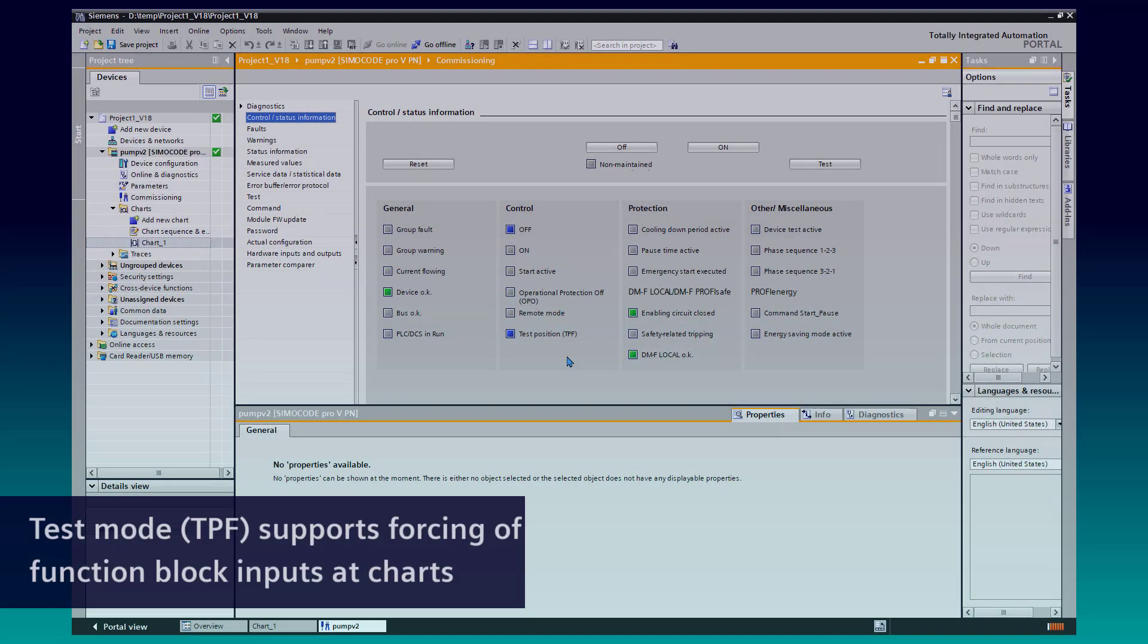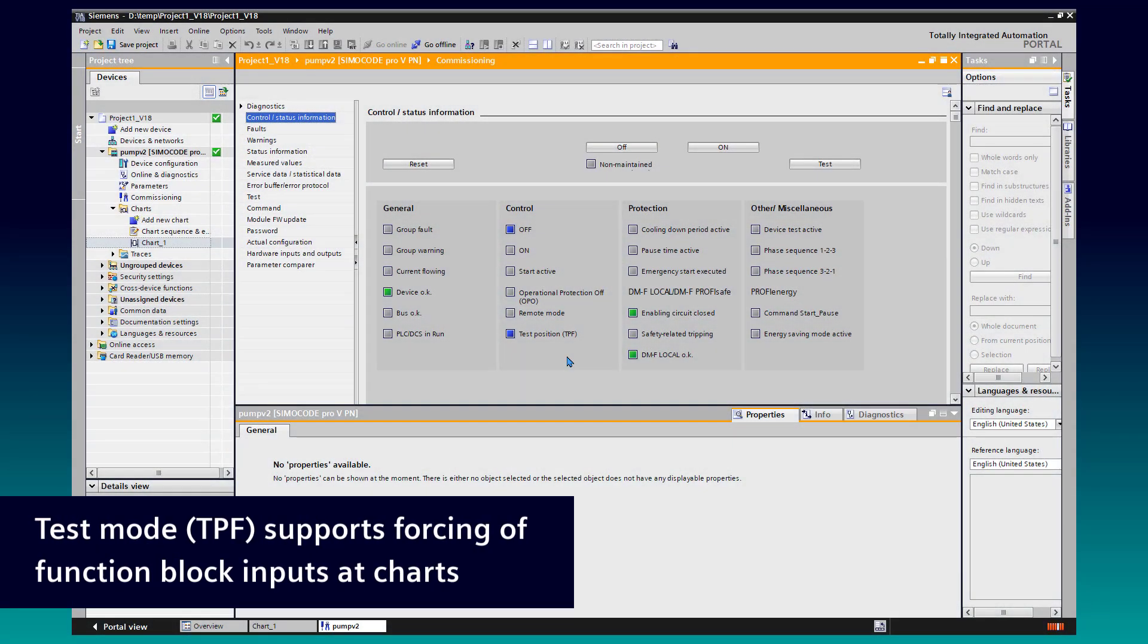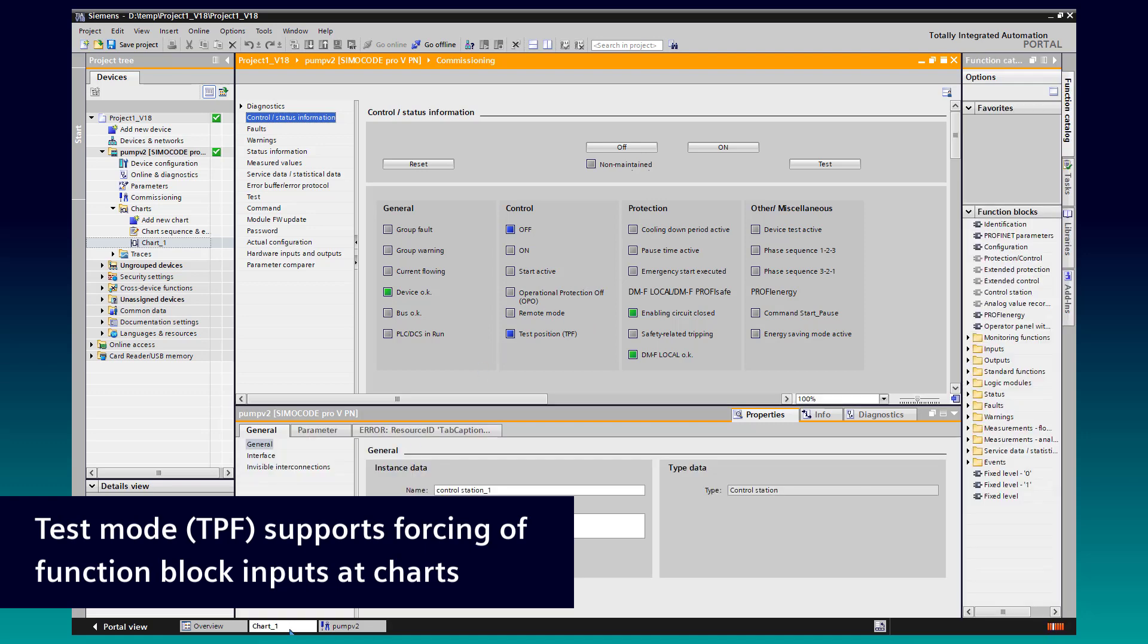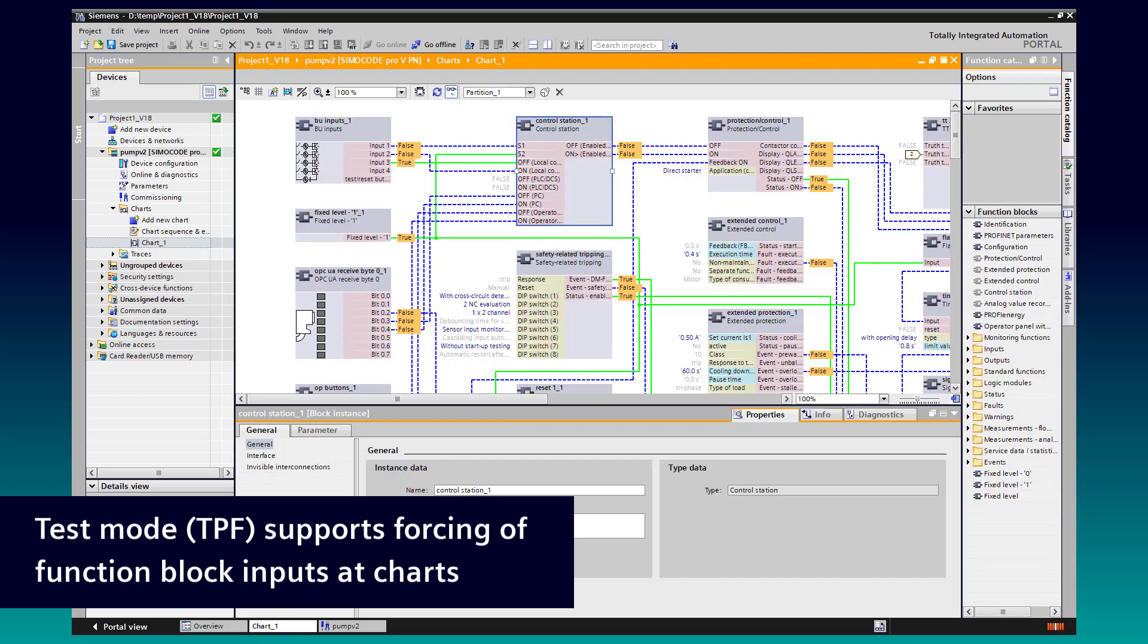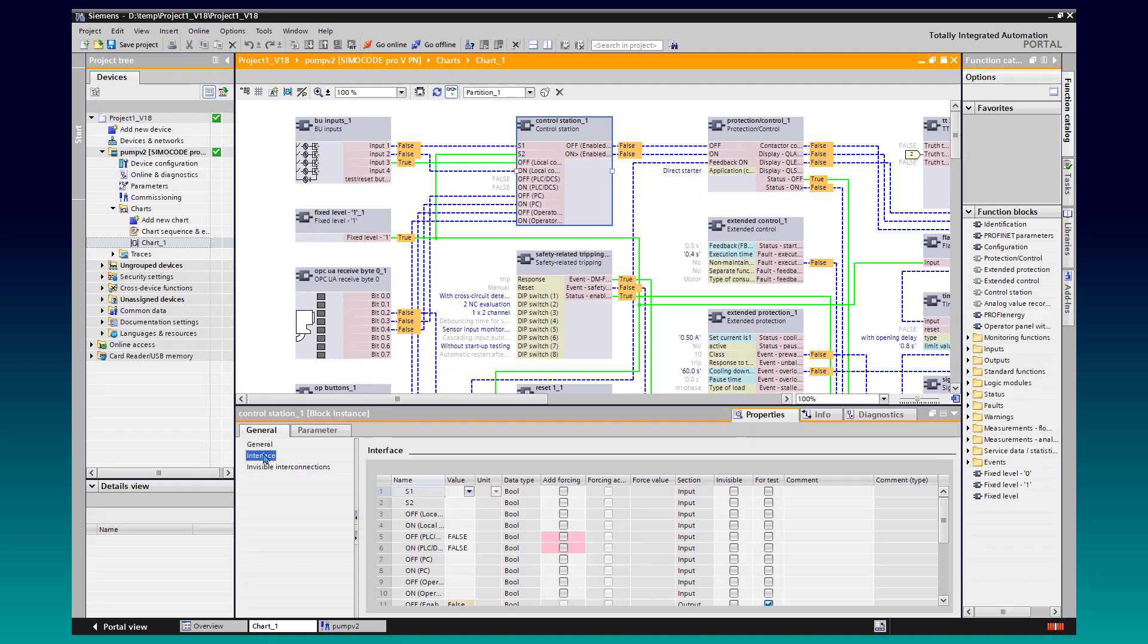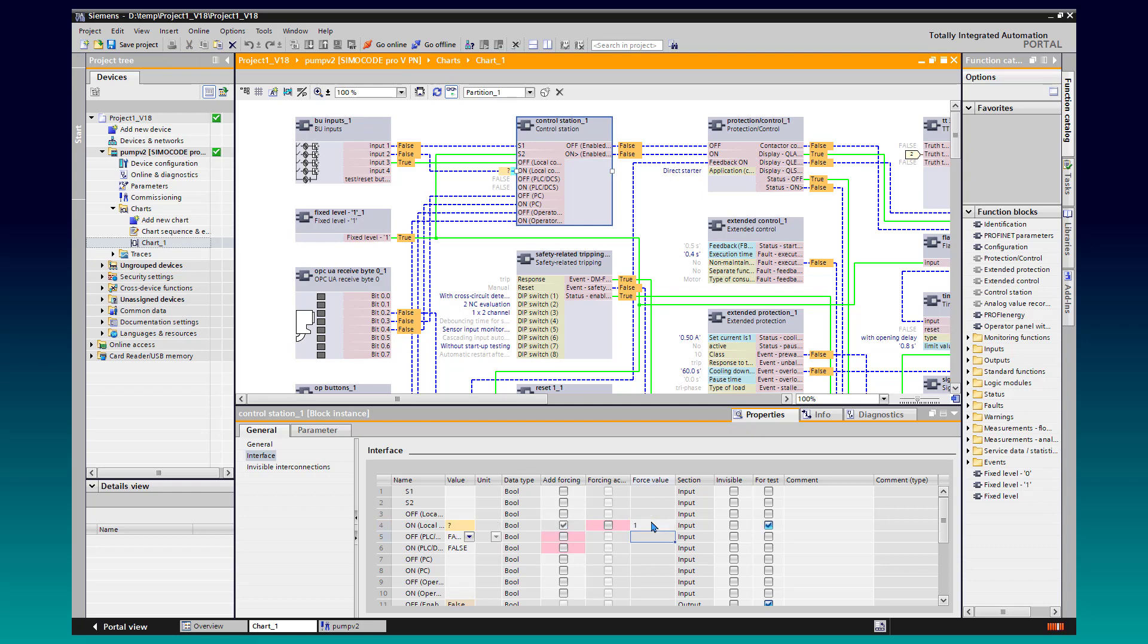At the chart view, it is now possible to force function block inputs when test mode TPF is activated. We switch to the chart and select the block where we want to control the inputs. At the lower window, we navigate to properties and interface. At the interface list, we can select the inputs we want to control and enter the value. With Enter, the value gets forced.